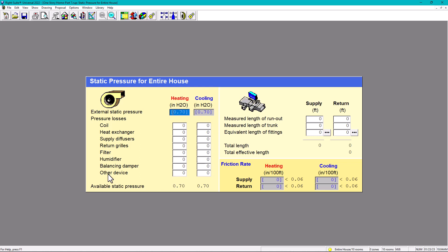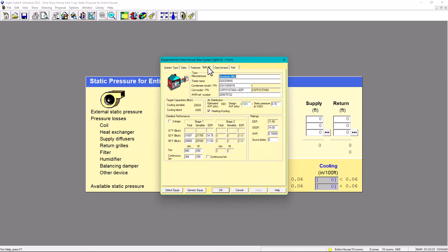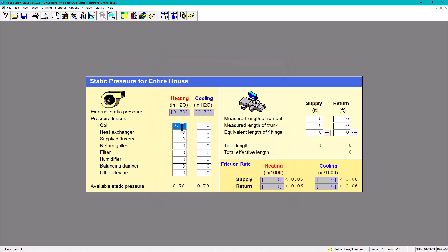In one of the previous videos, I already calculated the coil loss, and I also went into more specifics which was an interpolation process. Under that interpolation process and for this coil, we have the model number - everything is based on the model number. If you don't have the manual, you can always contact a rep and they will provide it. The coil loss was 0.22 inches of water column.